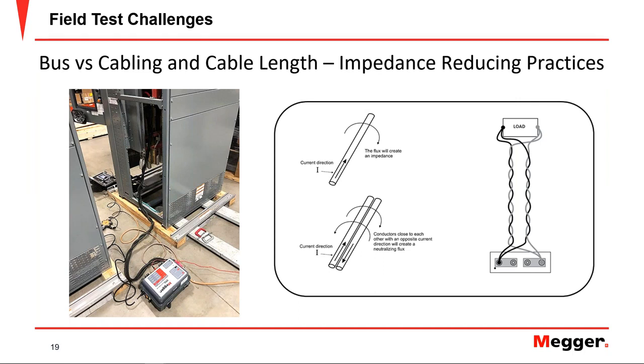We also need to avoid loops, especially when using long cables, such as the picture you're looking at right now. This configuration might seem strange for those that don't have a lot of experience, but this is a picture taken when the SPI was being used to test the ground fault protection element on a medium voltage circuit breaker, which by standard we can do with up to 1200 amps of current. So that's why we can use the SPI, and hence the long cables. And you see the cables are twisted, right? That's another recommendation to minimize the impedance of the circuit we connect to the SPI, and maximize the current that the unit will be able to inject.